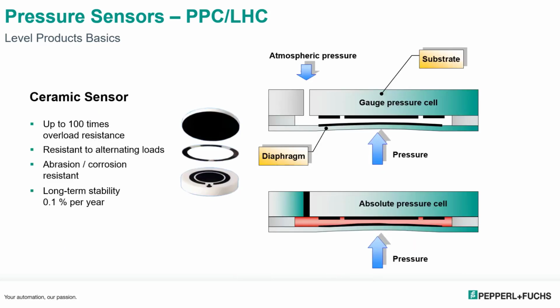The ceramic sensor that's located at the face of the sensor measures as the liquid rises, it produces more force on the face, and the ceramic sensor gives an output according to the pressure. And again, we can get these with a gauge output or an absolute pressure cell. They can actually take up to about 100 times overload resistance compared to the pressure that they're measuring, as well as resistance to alternating loads, hydraulic hits, and so on. They have a long-term stability of about 0.1% per year.